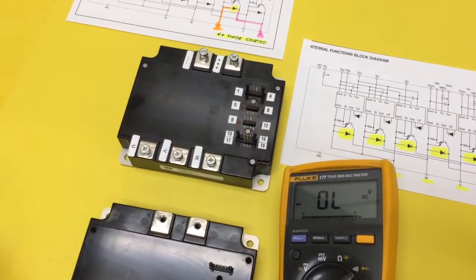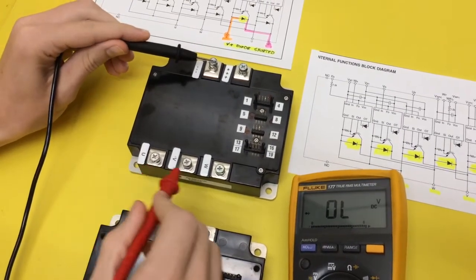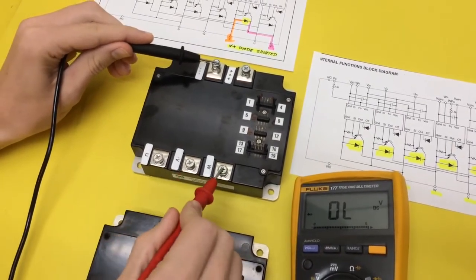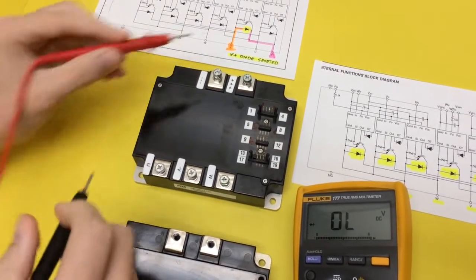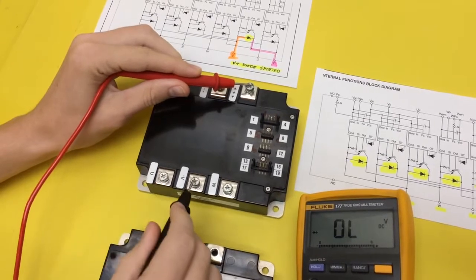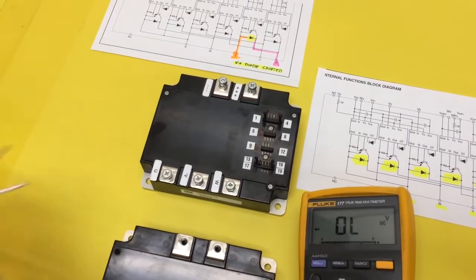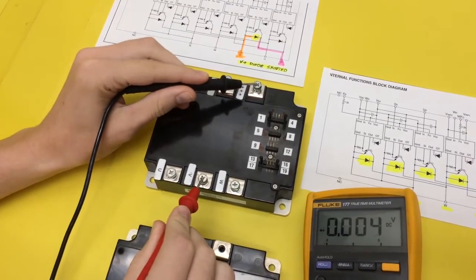Okay, so those tested good. Swap. Those all test good. Now we're going to get on the positive and here's where we're going to see our problem on V plus. So that reads bad. Go to W. Now swap your meter leads. Good, bad.